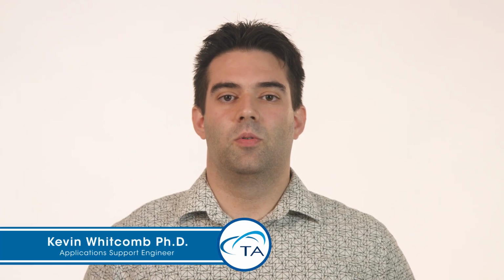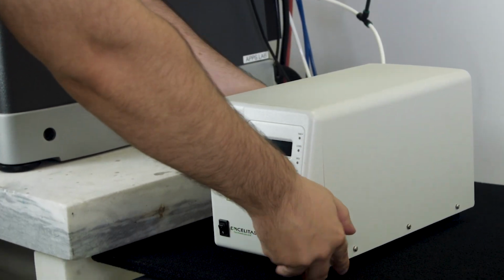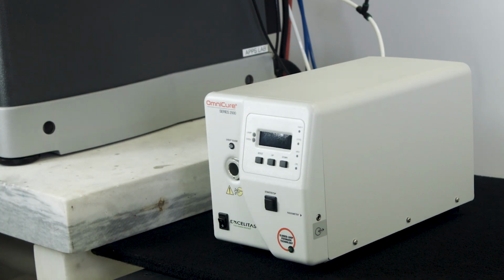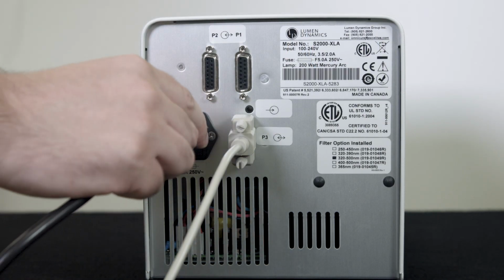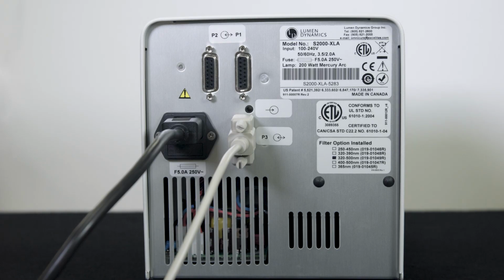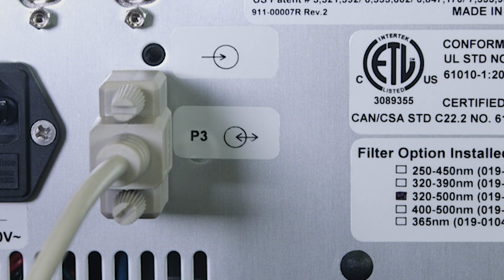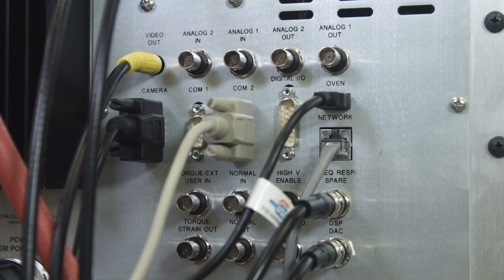In this Tech Tip, we'll show you how to install the UV Curing Accessory on the ARES-G2. To begin installation, place the light source to the right side of the instrument and connect the power cable. Next, connect the P3 port on the light source to the COM2 port on the instrument with the communication cable.